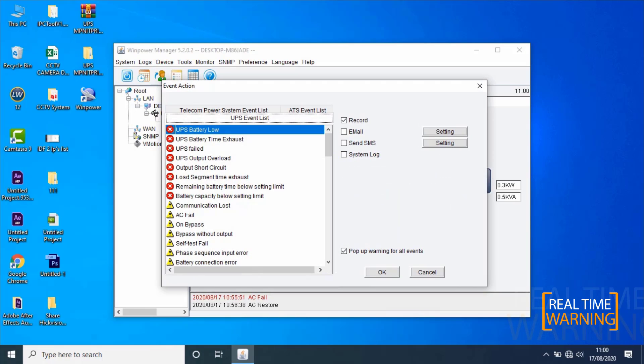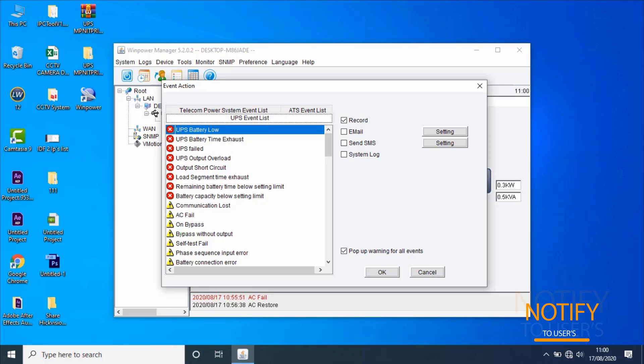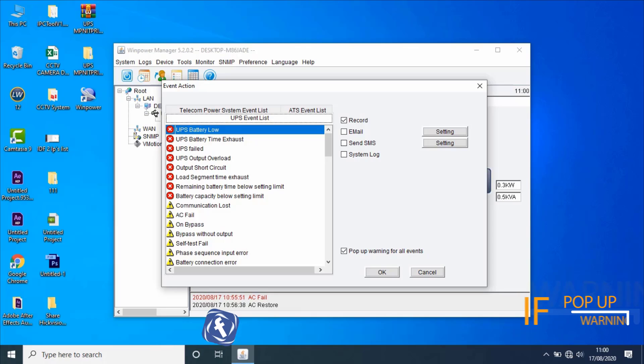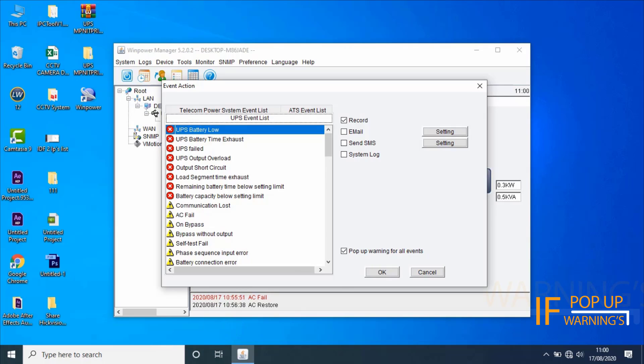Event Action is a real-time warning dialogue. When UPS status is abnormal, software will pop up a warning dialogue to notify the user. Warning dialogue on local computer means that the warning dialogue will pop up on the local computer communicating with the UPS when its status is abnormal. Open Event Action from the menu to set whether the warning dialogue pops up on the screen. If the option of pop-up warning for all events is selected, software will pop up a warning dialogue when an event happens, and on Linux OS there will be event broadcast messages shown on the terminal.